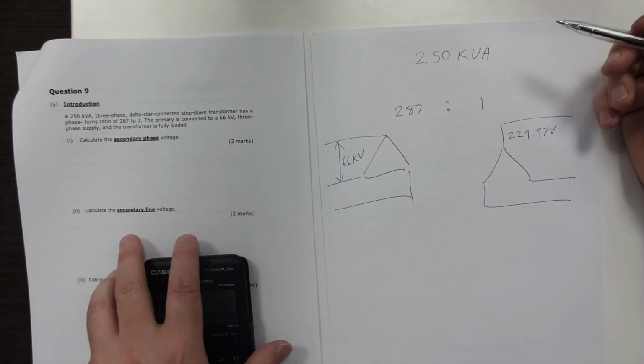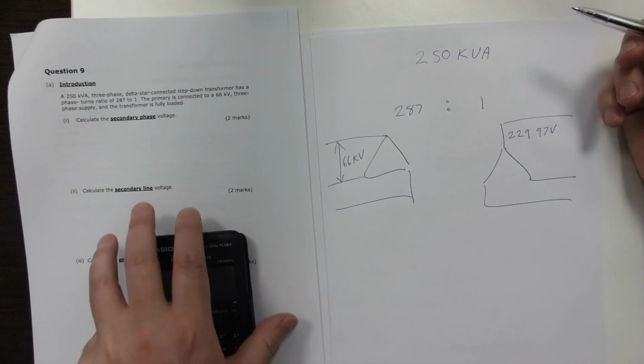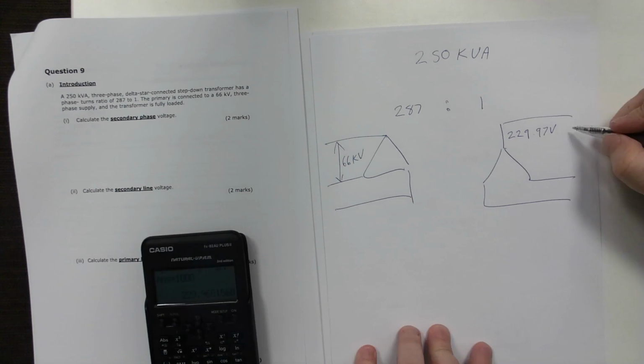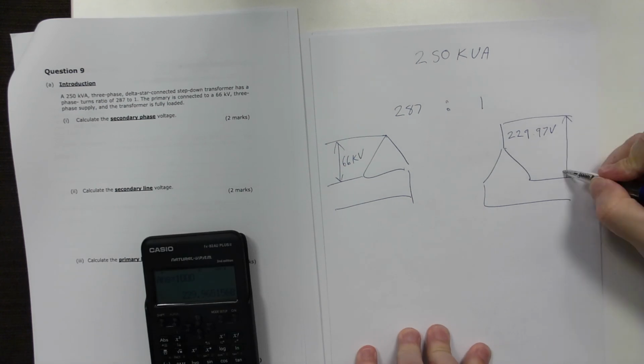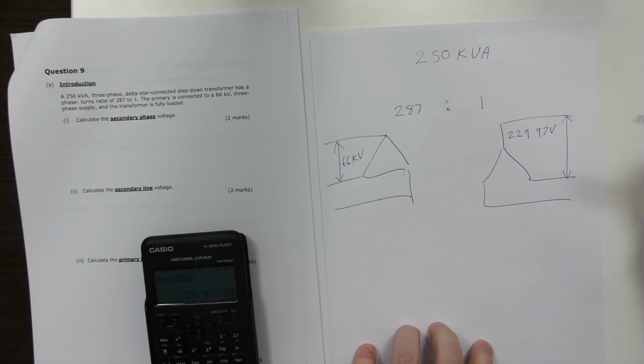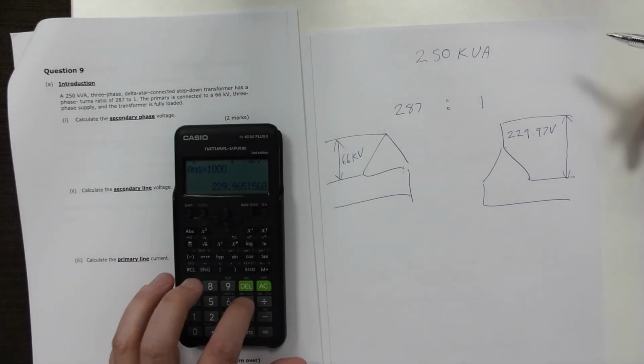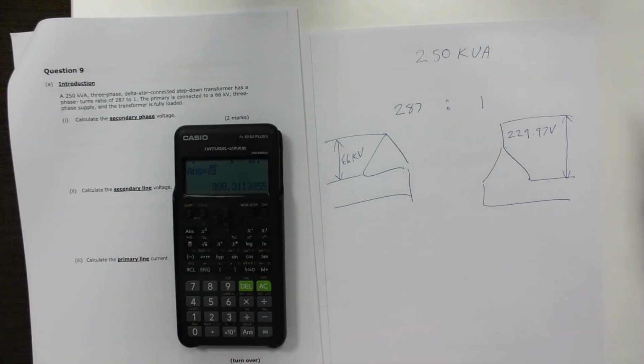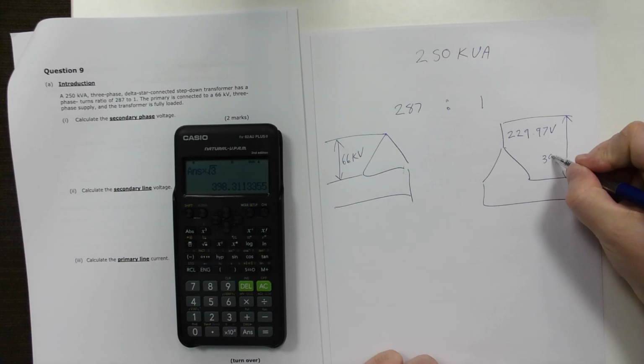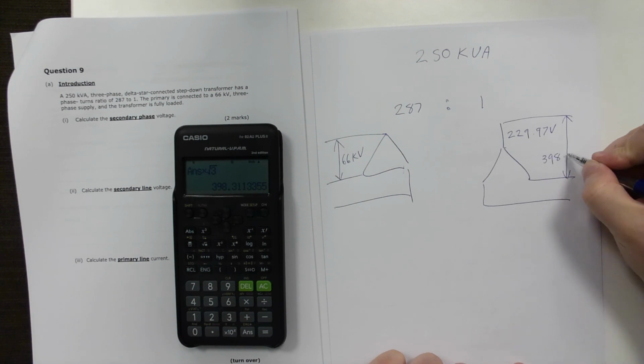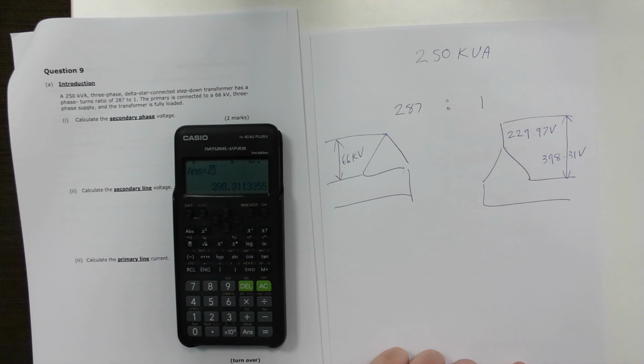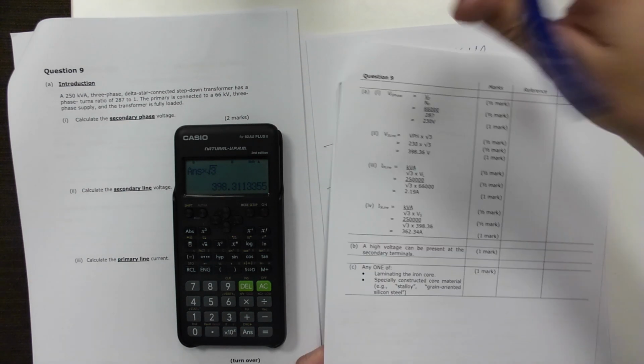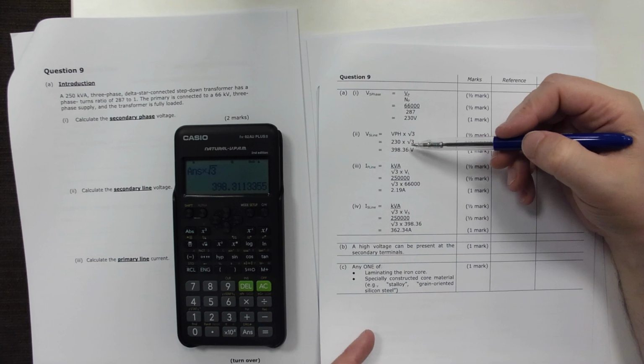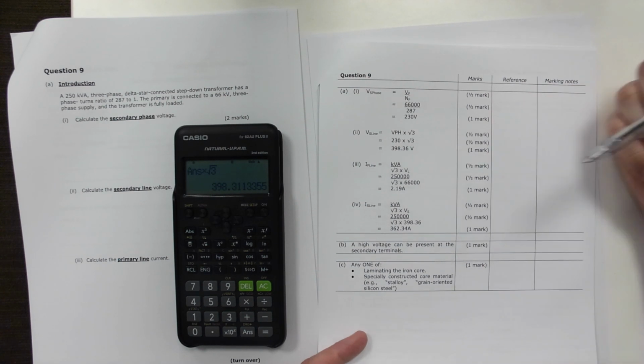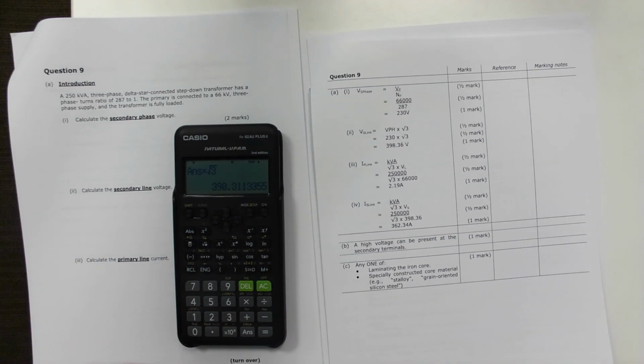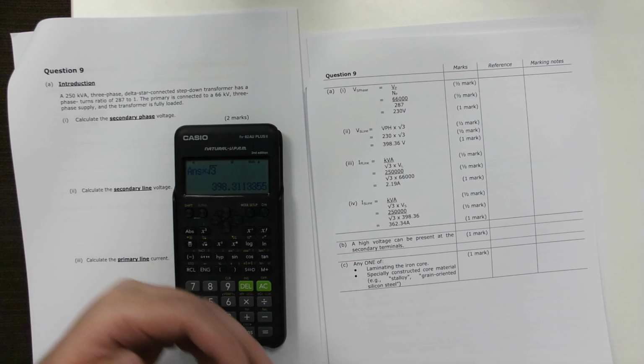Then we move on to the secondary line voltage. So line voltage is between there and there. It was phases that we were comparing before. So we times that by the square root of 3, and we get 398.311, so 398.31 volts. They had 398.36 because they rounded. Same answer, there's a level of fudge when you're doing these exams.